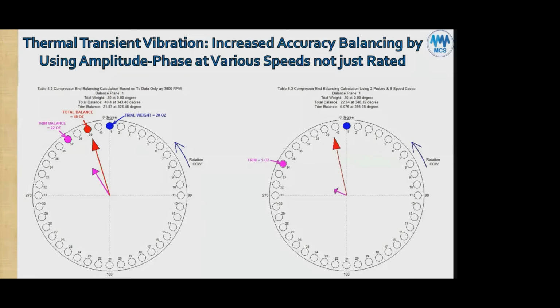Here it's a variable speed machine because it's gas turbine driven. So this must be a cold balancing, because they're balancing at the compressor end. They don't have to balance the generator with electric power going through it. If they're going to balance the generator, they're going to have to run it at 3,600 RPM only, and then vary the load, and then get that. But in this case, they're not trying to balance the generator.